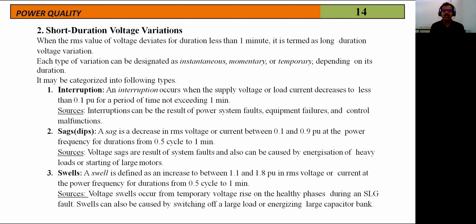The sources of interruptions can be the result of power system faults, equipment failures, and control malfunctions. It is majorly due to power system faults, equipment failures, and control malfunctions. For example, if the capacitor banks are not switched properly. Similarly, power system faults due to LG faults, LLG faults, triple L faults, etc. Equipment failures: any equipment, either transformer or transmission lines, etc. Any equipment that fails comes under interruption. For the interruption, the time period should be less than 1 minute.